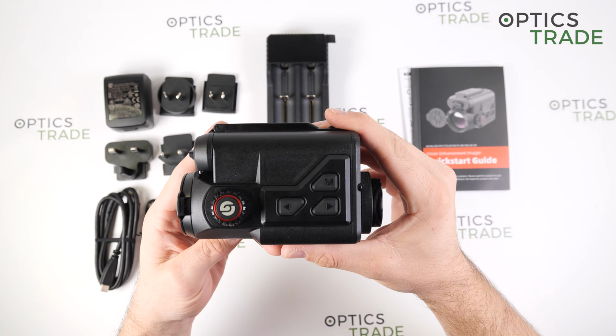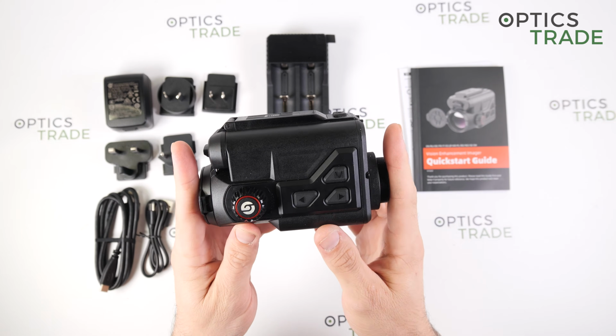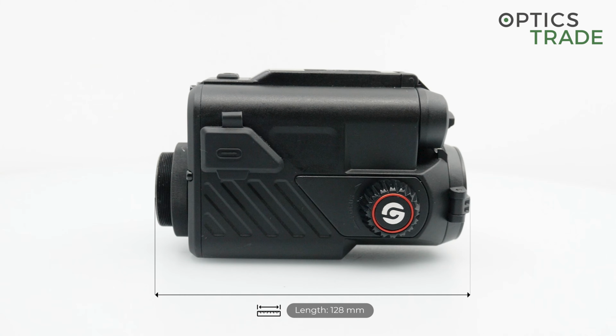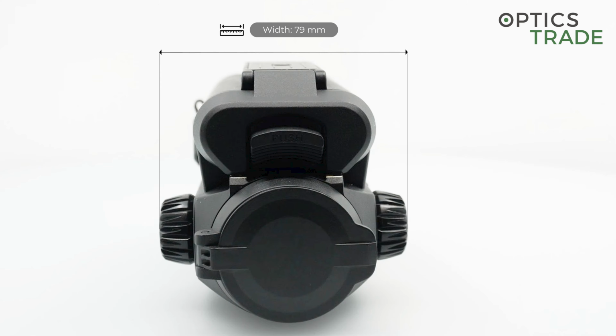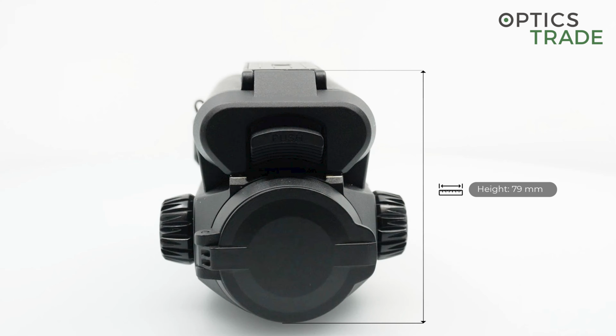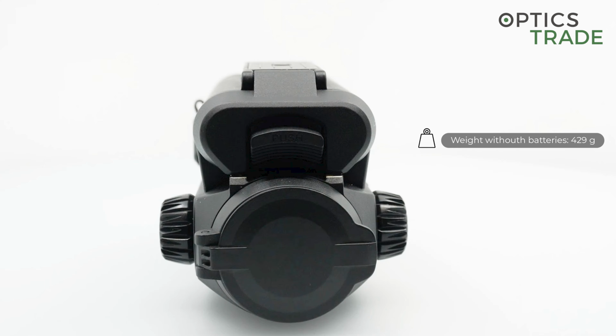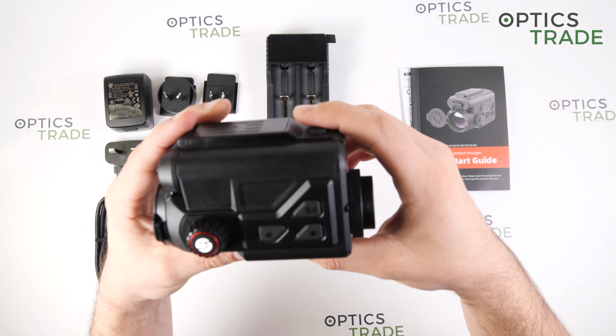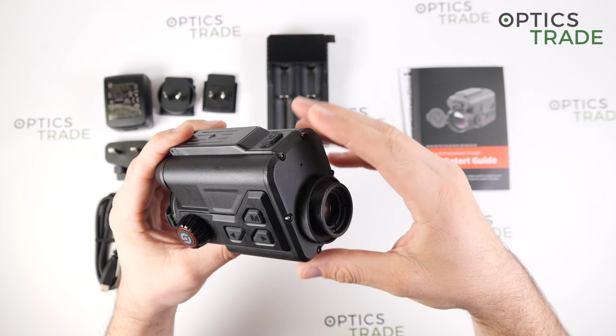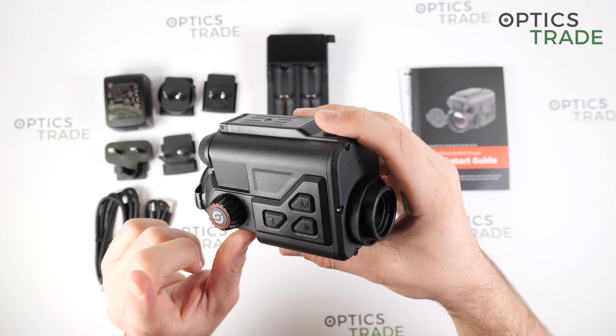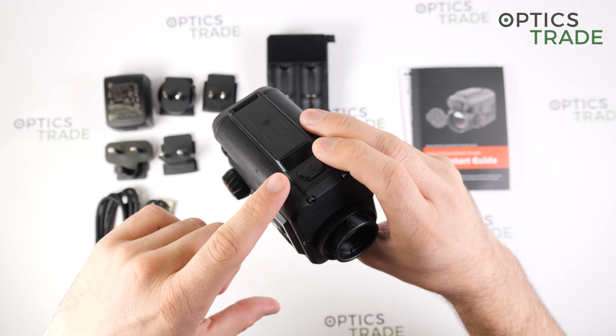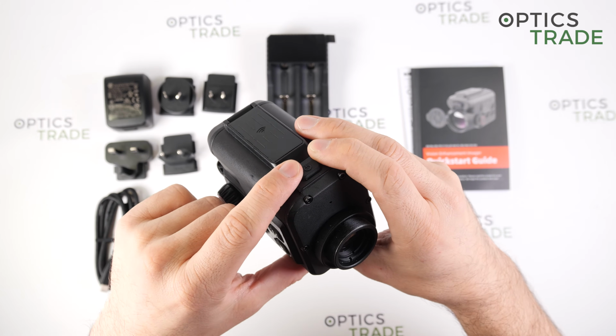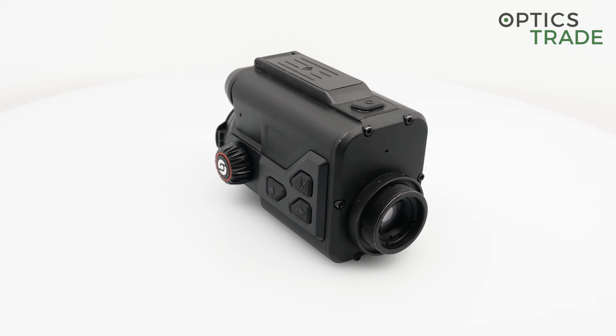problem for the device. Now for the size, in length, the device is 128 millimeters long, and it is 79 millimeters wide, and the height is also 79 millimeters. The weight is also quite small, with 429 grams without the batteries, and with the batteries included it's 529 grams. The startup time of this device is approximately 13 seconds. When you press the button, first you have to wait with the black screen, then the logo from Guide appears, and from then on it's approximately 5 seconds.